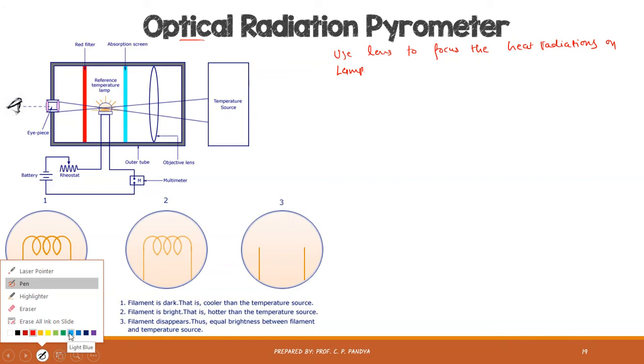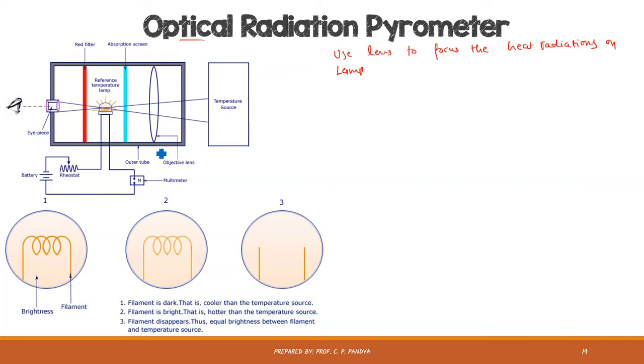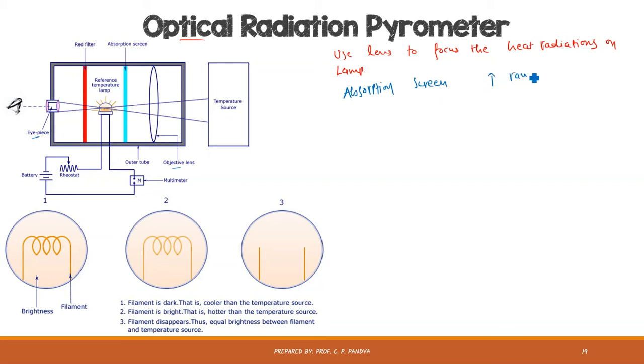As far as the construction of this pyrometer is concerned, it has two lenses: the first is the objective lens and the second is the eyepiece lens. The objective lens is used to focus the rays emitted from the source onto the filament of a lamp. The lamp serves as our reference temperature against which we measure the actual temperature of the source. Between the lamp and the objective lens, an absorption screen is used to increase the range of measurement.